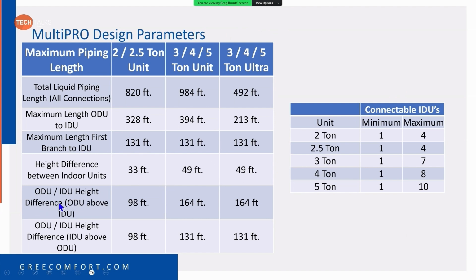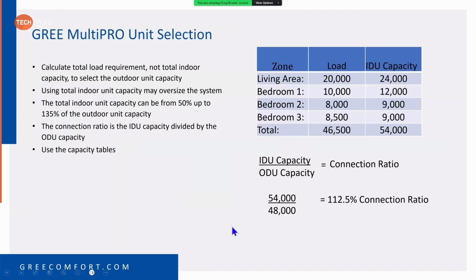Outdoor unit to indoor unit height difference, outdoor unit above or indoor unit above. These are your differences. You can go 98 feet on 2 and 2.5 ton standard, 164 feet with the outdoor unit above, 131 feet when the outdoor unit is below, and on the 3, 4, and 5 ton, it's the same as far as those requirements go. Oh, let me go back.